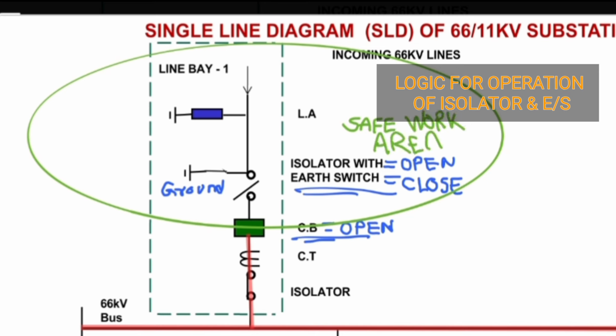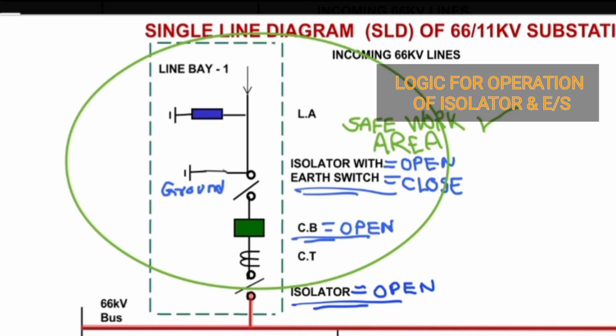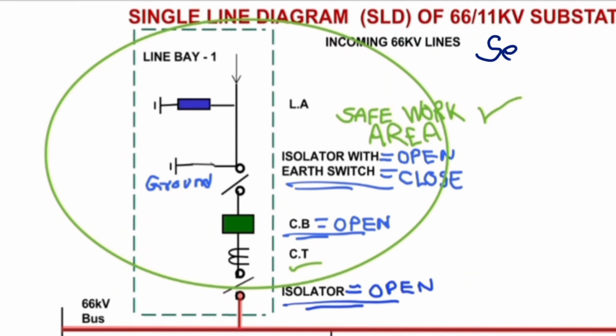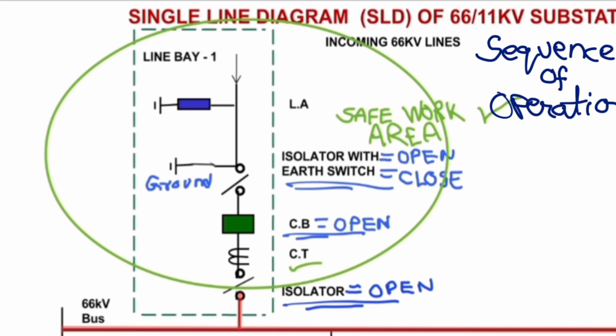But if work is required to be done on the CT, then the line's bus isolator should be operated and made open. Then the current flowing is shown like this. The diagram clearly indicates the safe working area, where any maintenance activity can then be carried out. From this, we can understand the sequence of operation of circuit breaker, isolator and earth switches.